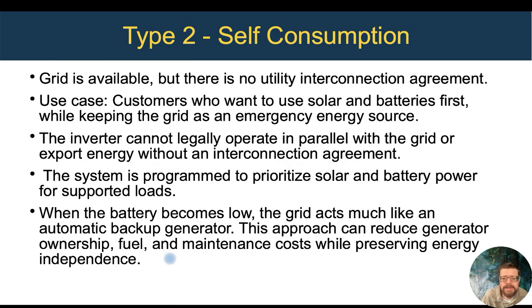Looking at the next type, this is the type 2 self-consumption. We've got the grid available, but we really don't want to use it unless we just run out of solar power. And because we don't have an interconnection agreement, we can't operate in parallel with it. So we're essentially treating the grid as a backup generator in this case, and we want to wire that grid into the AC smart load 1 input, not the AC in, where it operates in parallel with that source. That means we can never accidentally backfeed the grid. All we're doing is basically switching back and forth between the grid and solar.